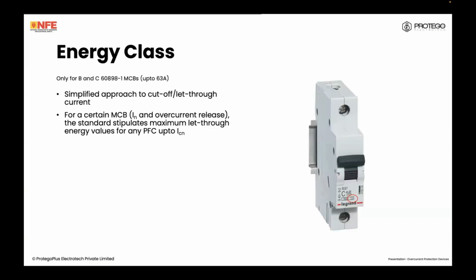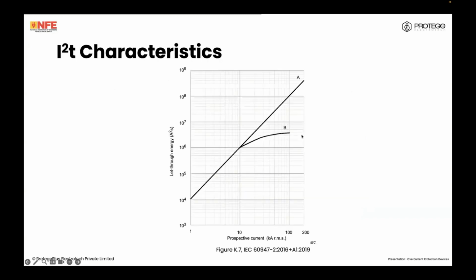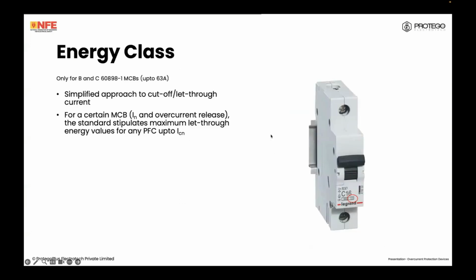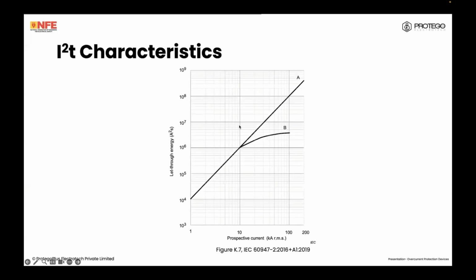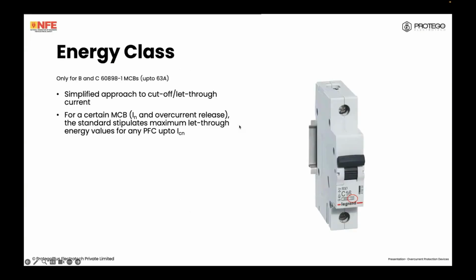Now there is the energy class, which is only for B and C curve 60898 MCBs up to 63 amps, obviously. This is a simplified approach. If you look on the MCB, there's this little box here with 3 here, which is what I've circled. What this means is that for a defined MCB, say a C16 MCB, which is type C to 60898 part 1, there is a certain maximum amount of let through energy. So beyond this, whatever the fault current up to the ultimate breaking capacity, there will only be this much let through energy allowed in the circuit, which is what these current limiting breakers do, and energy classes are a simplified approach to that.